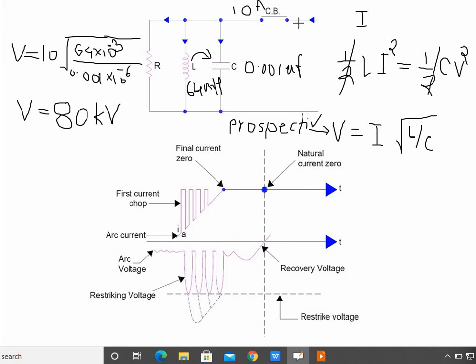Now we can see here the magnitude of this prospective voltage V is quite high. If this voltage is high enough to break down the dielectric between these two circuit breaker contacts, then that will lead to the restrike of the arc in the breaker, and so the current will start to flow through the circuit again.